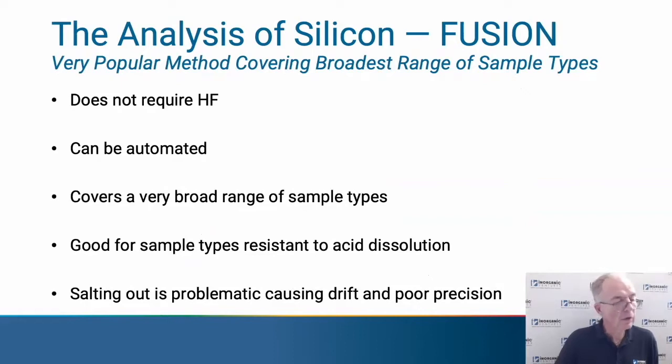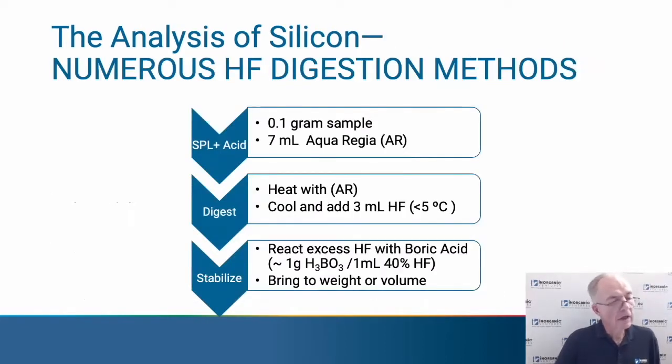And the only thing we can really say is it can be problematic with respect to salting out, but that's not necessarily the case. It depends on dilution of the sample with the flux and the type of introduction system you're using. Now, the other method that we'll be talking about and comparing is acid digestion.